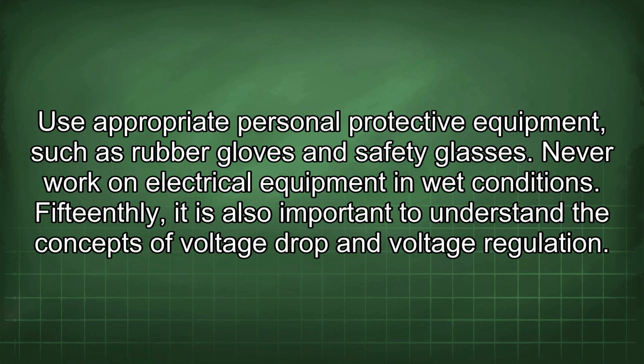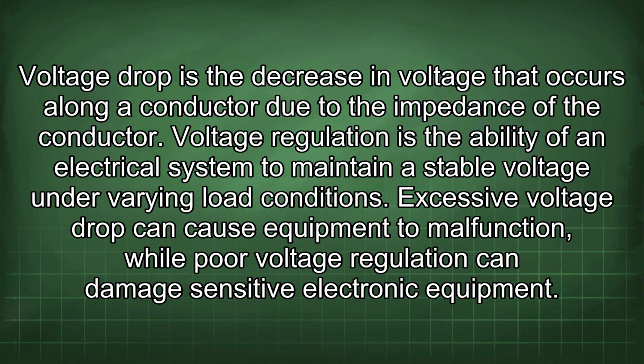15thly, it is also important to understand the concepts of voltage drop and voltage regulation. Voltage drop is the decrease in voltage that occurs along a conductor due to the impedance of the conductor. Voltage regulation is the ability of an electrical system to maintain a stable voltage under varying load conditions. Excessive voltage drop can cause equipment to malfunction, while poor voltage regulation can damage sensitive electronic equipment.